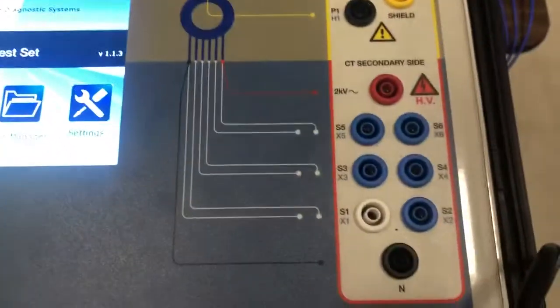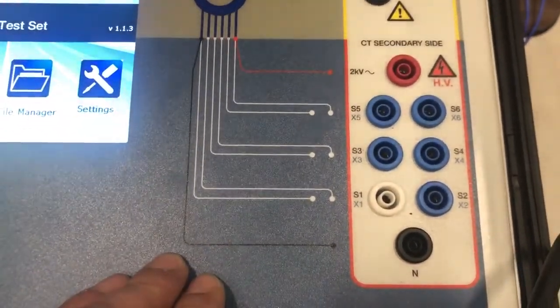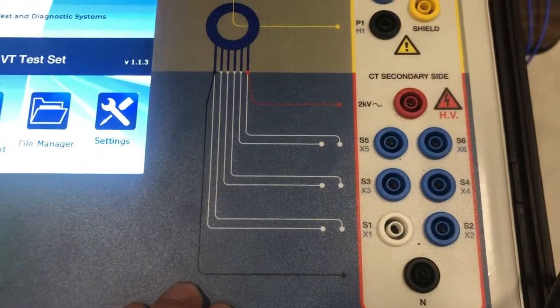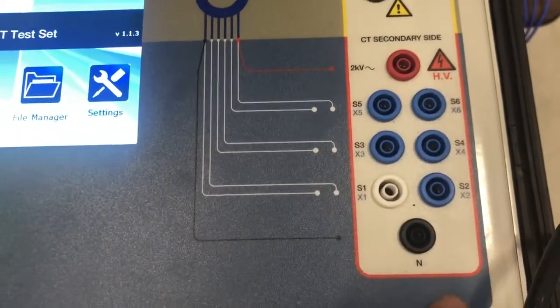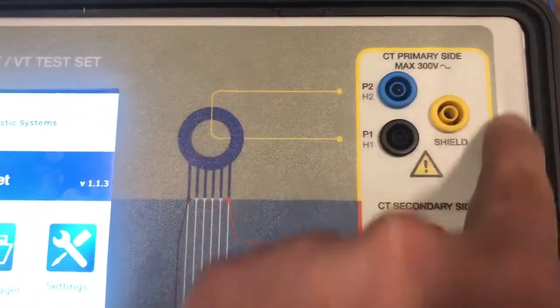First of all, since we are using volt method to test the ratio, the red sign here says that this is where we will be doing the generation from. So we will generate on the secondary side and we will measure on the primary side.